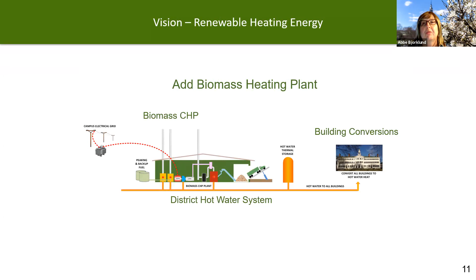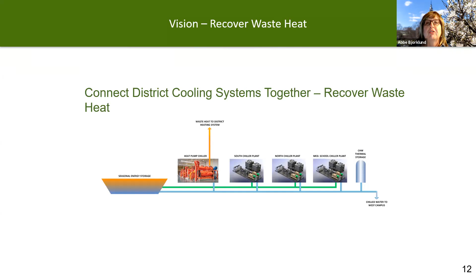Another key part of the 2016 study was to interconnect our chilled water plants and buildings on campus and install heat pumps, as Jim was talking about at Amherst, to utilize the waste heat from the condenser side of the heat pumps to provide heat to our heating network and cooling to our chilled water network, and to exchange heat between buildings through those networks.